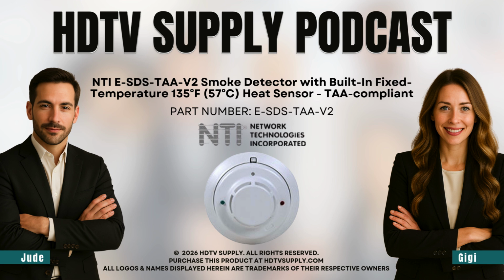And they've even specified the temperature threshold. It's 135 degrees Fahrenheit, 57 degrees Celsius. And that number is so deliberate, because it's not a normal house fire temperature. It's engineered to live in a hot environment without constantly crying wolf. Precisely, it defines the danger zone for IT equipment specifically. So when either that heat threshold or the smoke sensor gets breached, it sends a signal to the larger EnviroMUX system, which then executes the pre-configured alerts. It's really the frontline environmental sentinel.